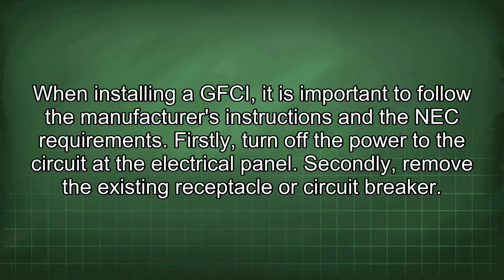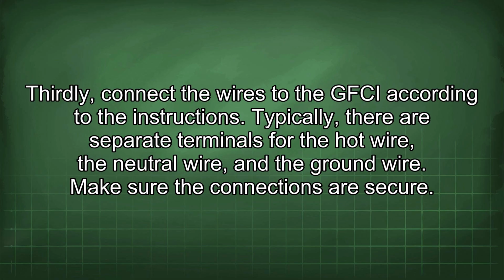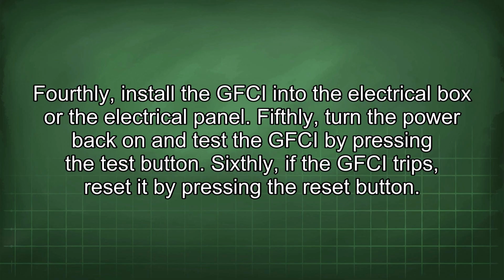When installing a GFCI, it is important to follow the manufacturer's instructions and the NEC requirements. Firstly, turn off the power to the circuit at the electrical panel. Secondly, remove the existing receptacle or circuit breaker. Thirdly, connect the wires to the GFCI according to the instructions. Typically, there are separate terminals for the hot wire, the neutral wire, and the ground wire. Make sure the connections are secure. Fourthly, install the GFCI into the electrical box or the electrical panel.